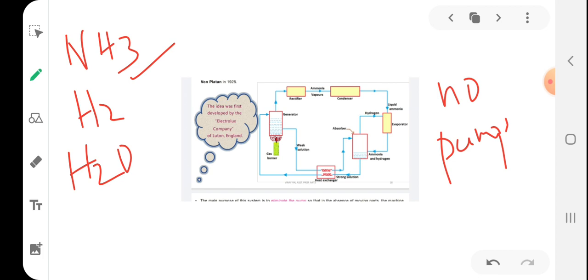Students, another gas called hydrogen is used here, because hydrogen is a very light gas, actually the lightest gas. The presence of hydrogen will enhance the rate of evaporation of the liquid ammonia passing through the evaporator, so the liquid ammonia evaporates easily. Hydrogen is also non-corrosive and insoluble in water, so there are no such problems. And water is used as the solvent or absorbent, because water can readily absorb ammonia.